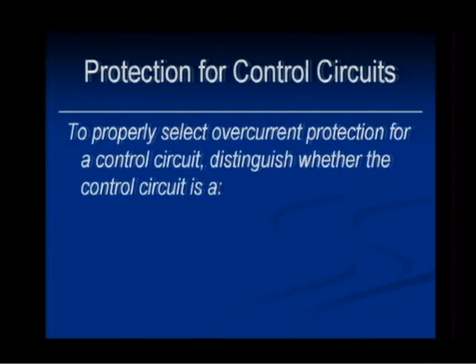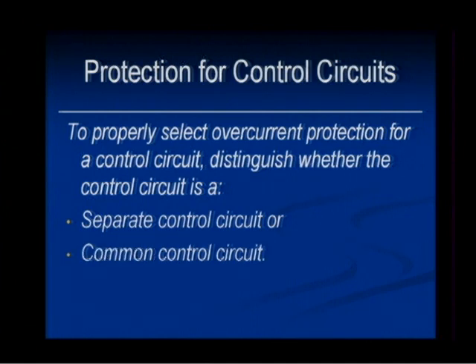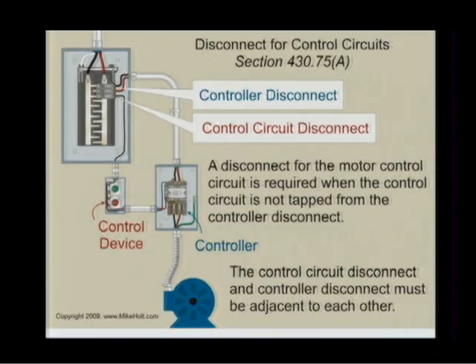To properly select overcurrent protection for a control circuit, distinguish whether the control circuit is a separate control circuit or whether it is a common control circuit. So let's kind of identify those two terms. First one is a separate control circuit. A separate control circuit, you can see right here, we're coming off the auxiliary contacts, getting our 3-wire control, 1, 2, 3, coming over here. Here's a neutral coming down, going to one side. Here is our overcurrent protection. So since we're providing a separate protection for these conductors, we have to size that protection based upon the ampacity rating of these conductors.